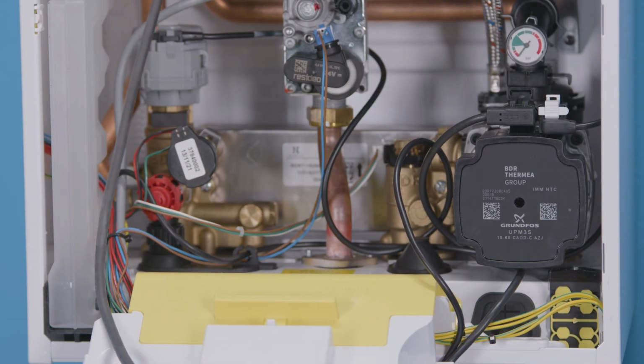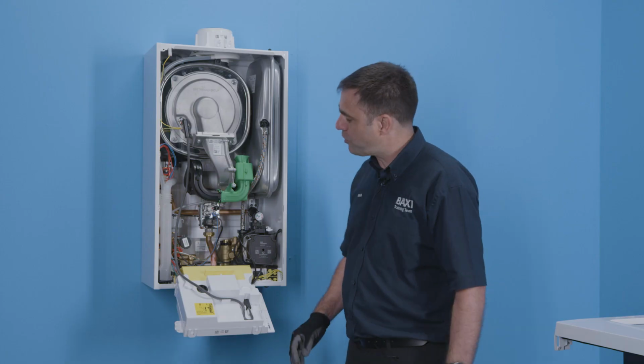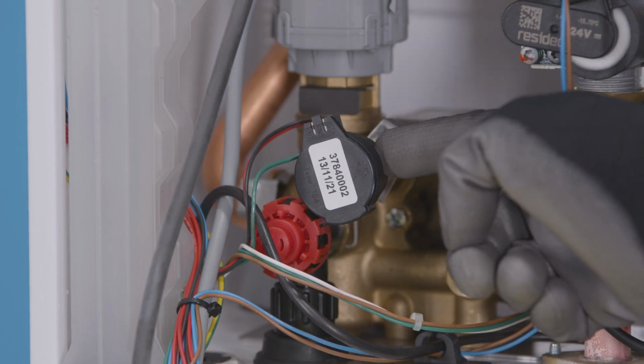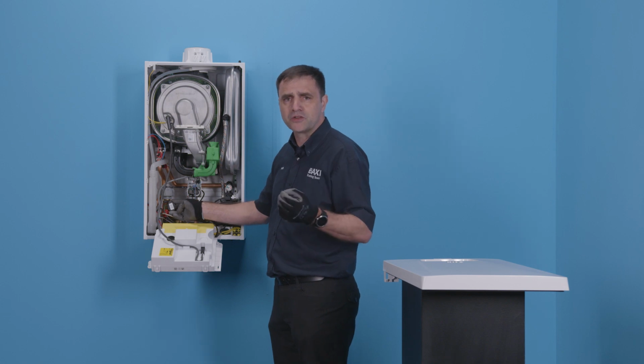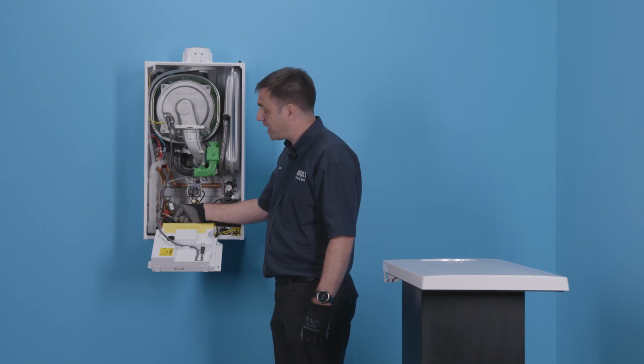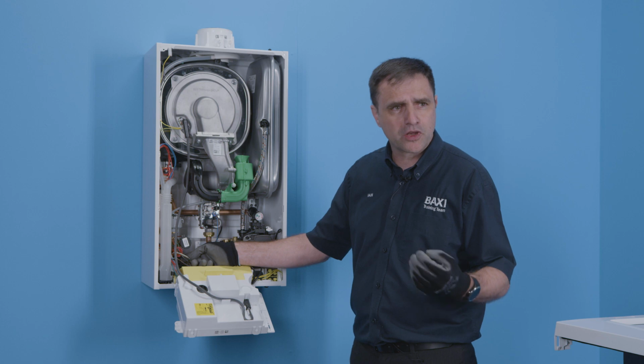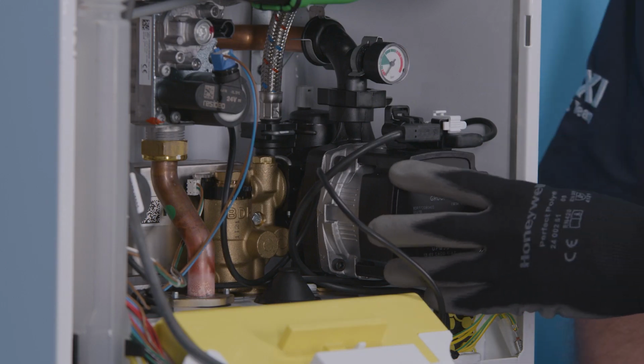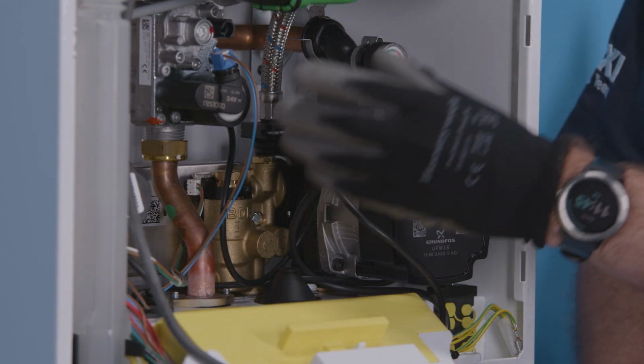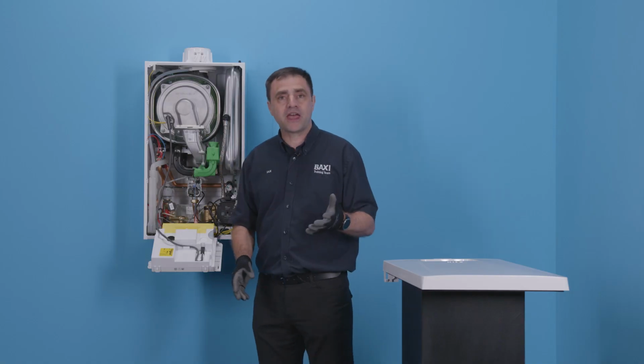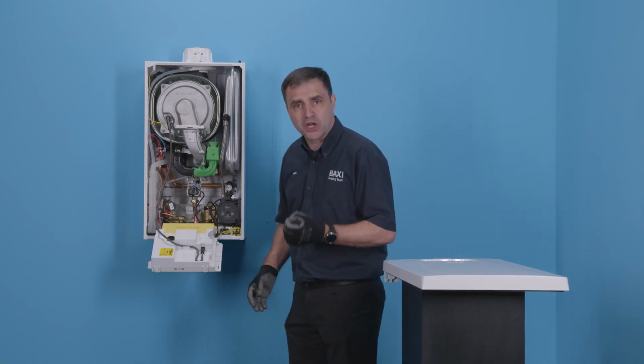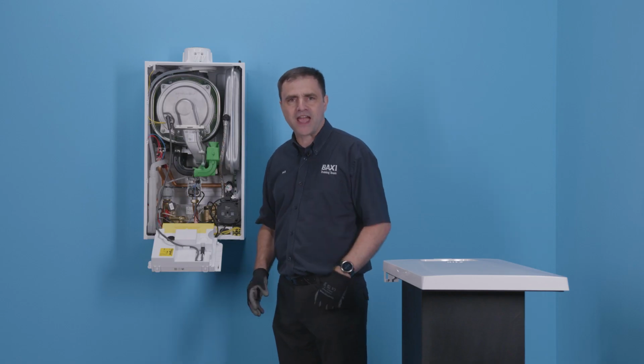Moving further down to the hydraulics, all brass, making it reliable. What we have here is a pressure sensor, meaning you can read the gauge on the front, and a drain point incorporated into the pressure relief valve. We'll be looking at that in more detail later. Fully modulating ERP pump and a Resideo gas valve. So what you see there is some familiar stuff and some new, building in that reliability we've built over years and improving where we can.